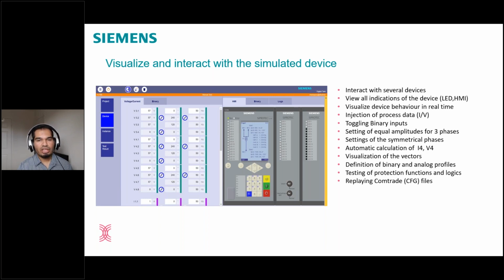You're able to inject process data, that is currents and voltages, and not only the magnitudes, you can also influence the phase angles and frequencies. You are also able to trigger or toggle binary inputs, and then maybe to give a status of a breaker close or breaker open, or maybe an intertripping requirement. You can do that as well.